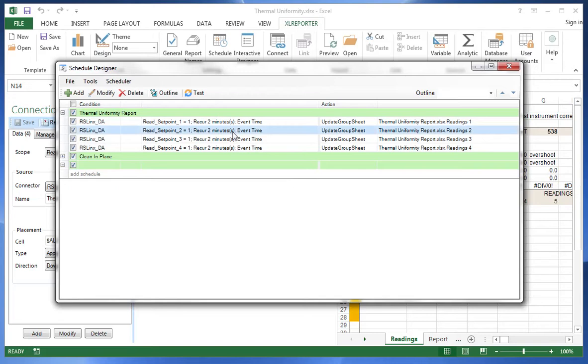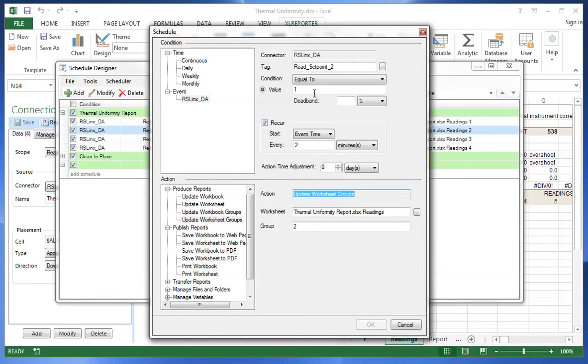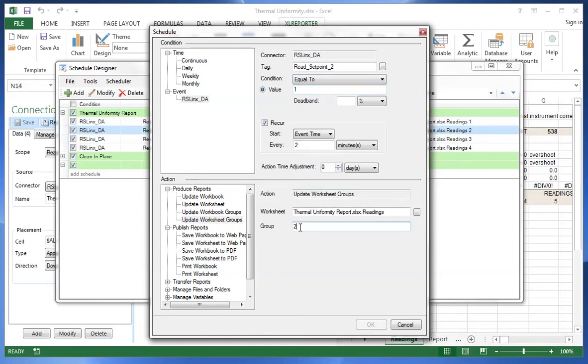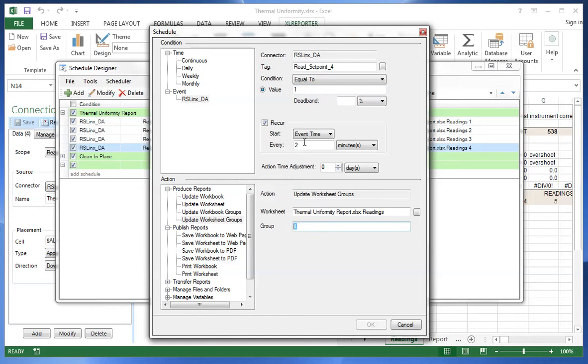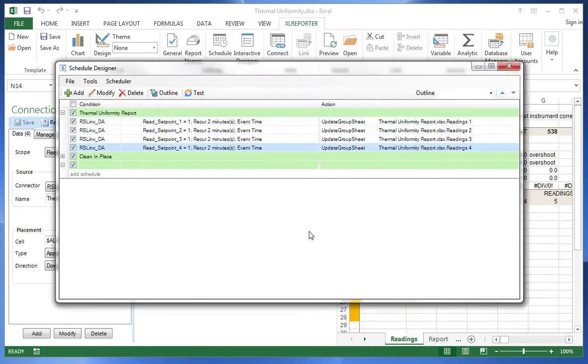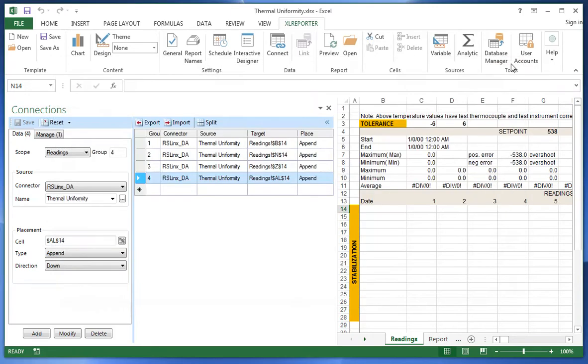For instance, here if the PLC bit called read setpoint 2 goes high, then we will update group 2 every two minutes. Likewise, if read setpoint 4 goes high, we will update group 4 every two minutes. So the population of the report is controlled by the PLC, putting this bit high and holding it there for the duration of the report.